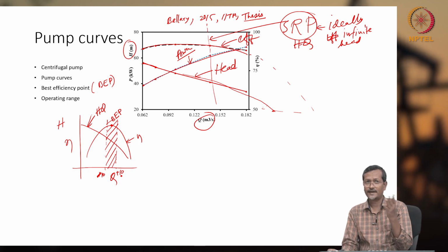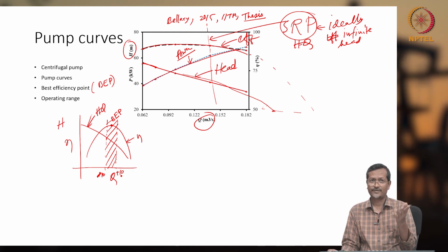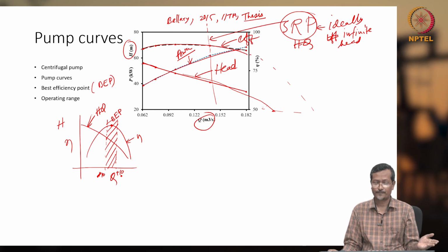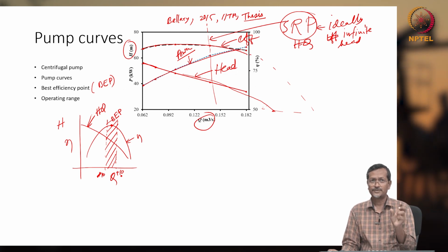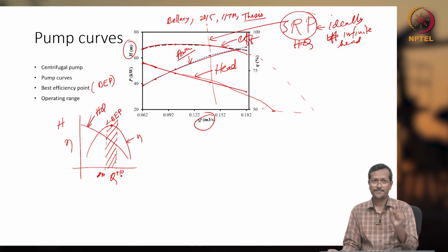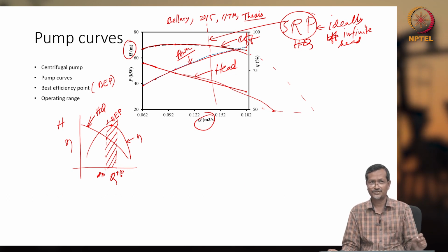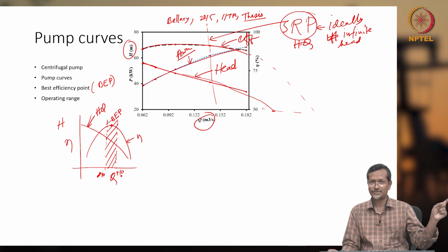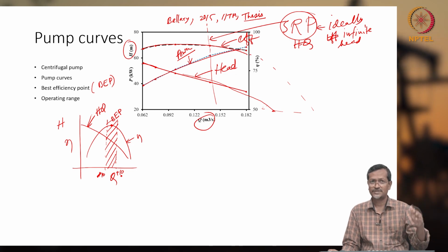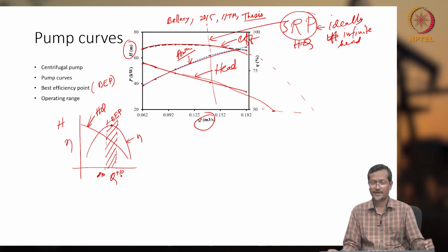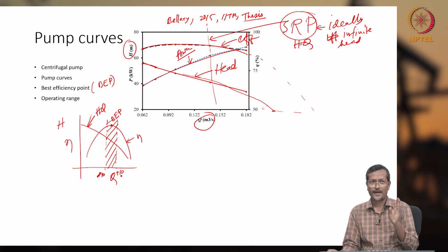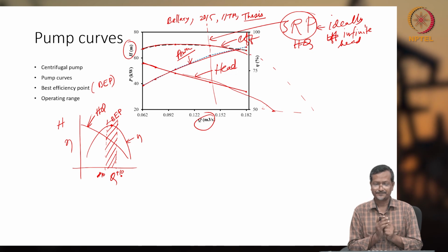Next thing is that it can create cavitation, noise, vibration, even the pump can fail also. So, your main purpose will be to run the pump at BEP. But if your flow rate or other things are changing, maybe you can try changing your pump speed. If you are changing pump speed, then flow rate and head and other parameters also can get changed. But at fixed speed, run the pump at operating range only.